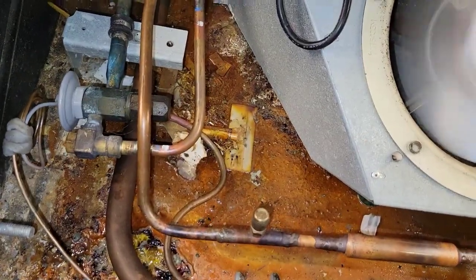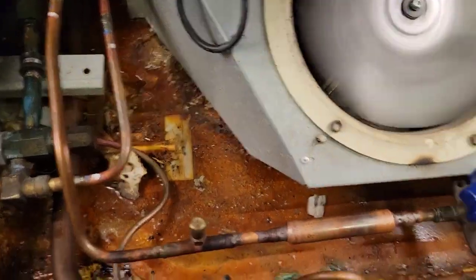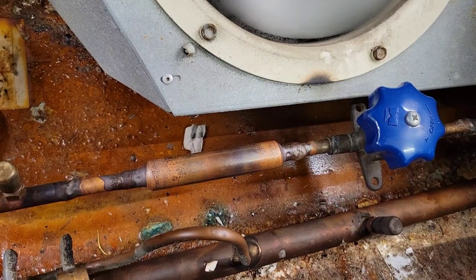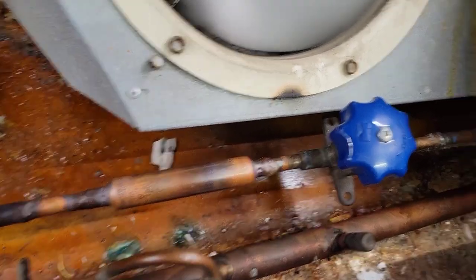All of them are spinning. Airflow is okay. I might lift up that last tile to double check. Also, while you're checking your airflow, you want to be taking stock of things you have. We have a TXV screen. We also have this inline screen, okay, instead of a filter dryer.